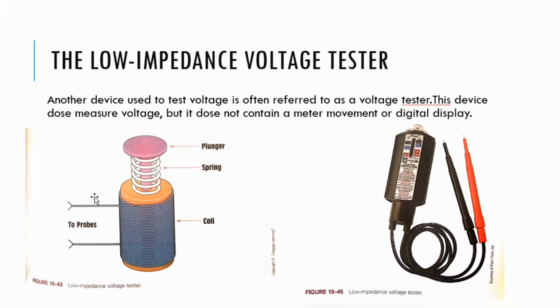Now, first we talk about this low impedance voltage tester, the internal diagram, you can say. This is the coil, the wire is wound on the iron core, and this is the spring which is under tension to pull the plunger up. When the voltage is applied to the coil, the coil attracts the plunger, and the plunger goes down, and the reading is shown in the range of voltage. And when the power supply is removed from the coil, the plunger goes back up to its position.